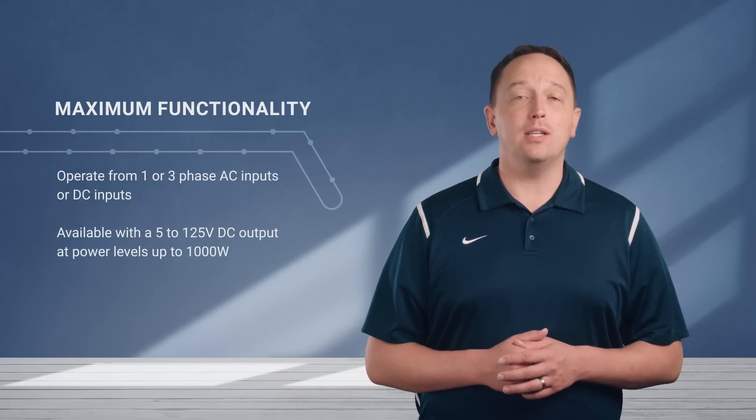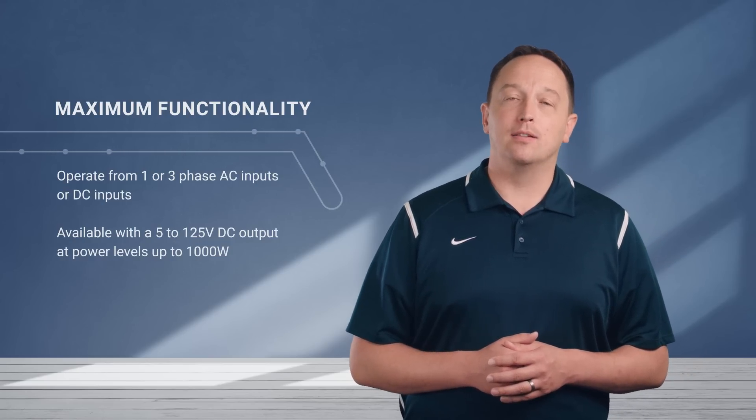Phoenix Contact Quint DIN Rail Power Supplies incorporate a number of technologies that provide maximum system availability and functionality. The power supplies can operate from one or three phase AC inputs or DC inputs, and are available with a 5 to 125 volt DC output at power levels up to 1000 watts. Quint power supplies include selective fuse breaking (SFB), preventative function monitoring, and power boost capabilities, and they can be configured via NFC.